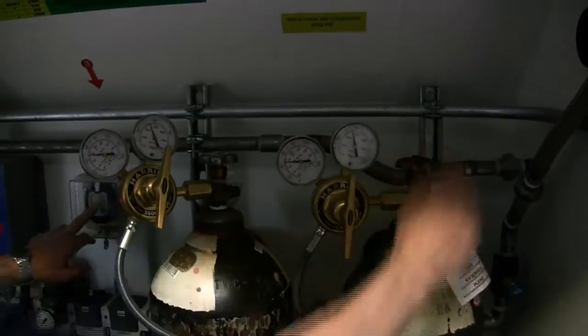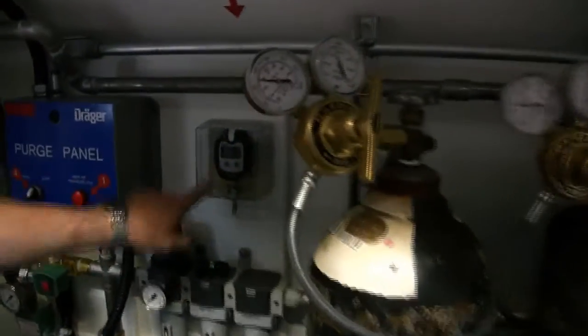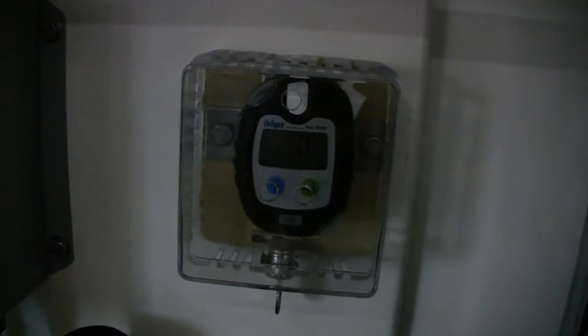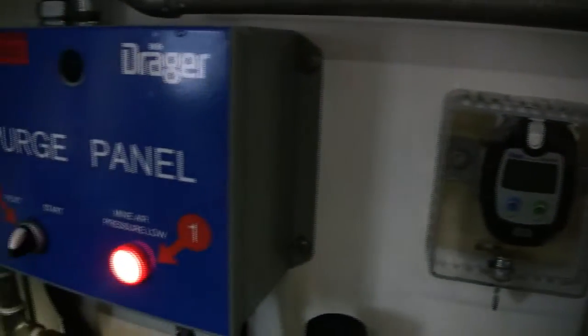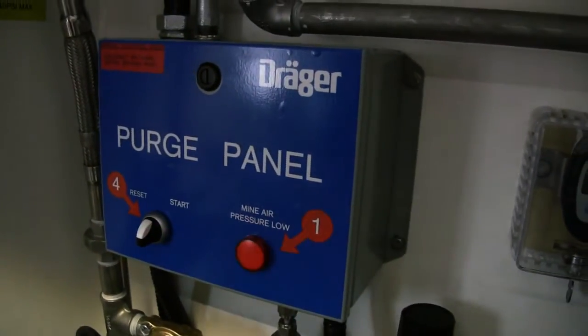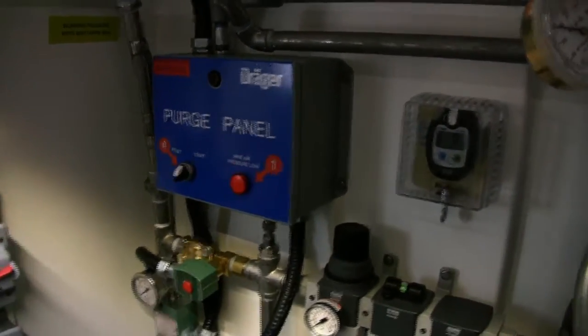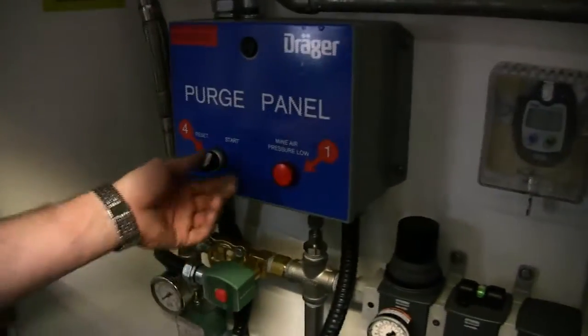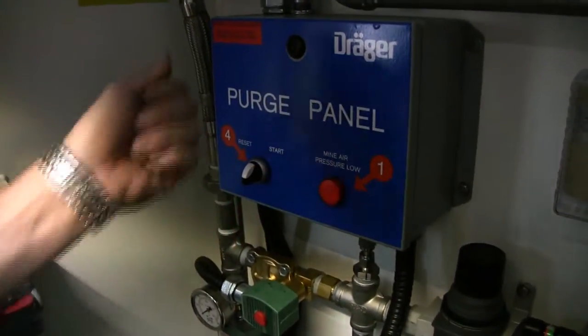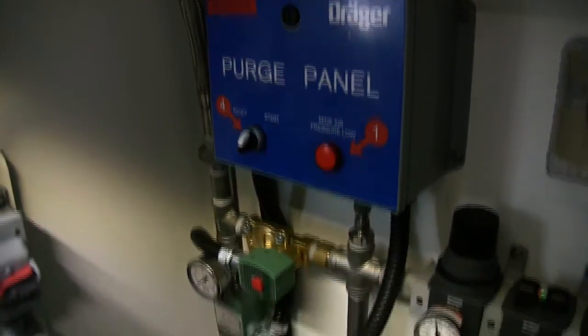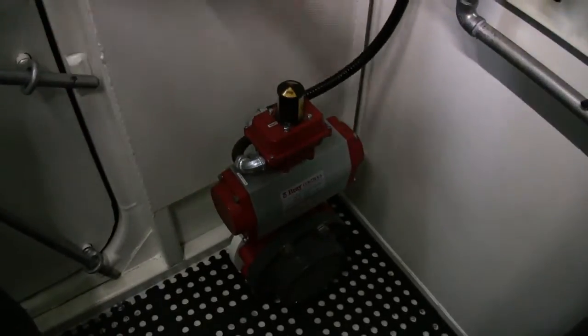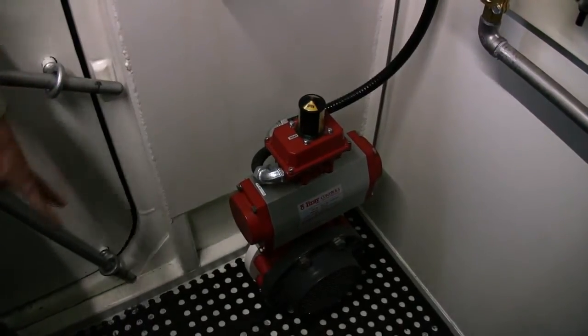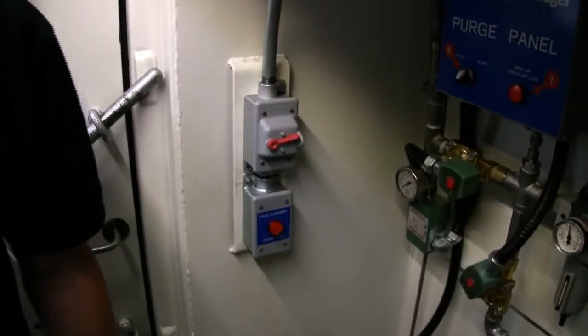There's a monitor here. This is showing you the carbon monoxide levels. So if that level is up you're going to purge. If the level is at zero you're not going to purge. If it's dusty or smoky in here then you're going to purge. How do you purge? Reset or start? Start. There's a valve at the bottom. This valve opens to make sure the room doesn't become pressurized. It's a very small room. It's 2,000 liters per minute of air rushing through.